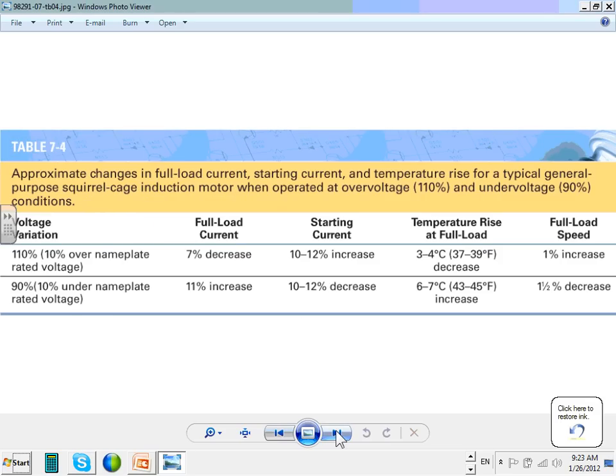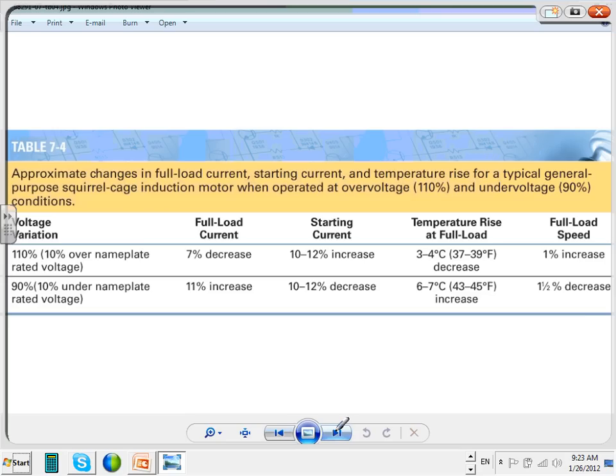One little thing, guys, this is really interesting, especially if you're a project manager. Decrease and increase in the voltage. The utility is supposed to give you plus or minus 5% in the voltage. Sometimes they go as high as plus or minus 10%. So they have to maintain a plus or minus voltage difference of 5% on the phases. Otherwise, your equipment starts getting nuts. Take this as an example.